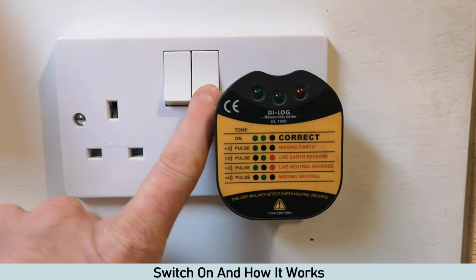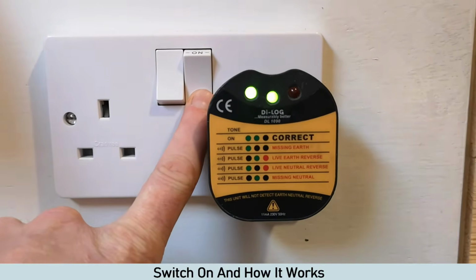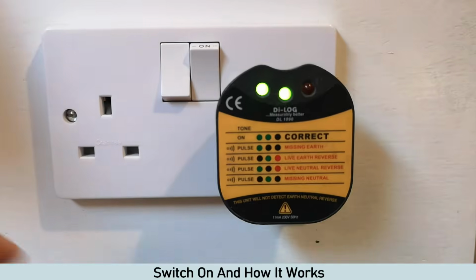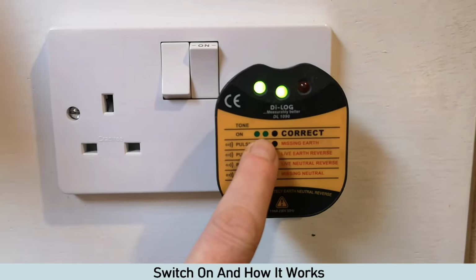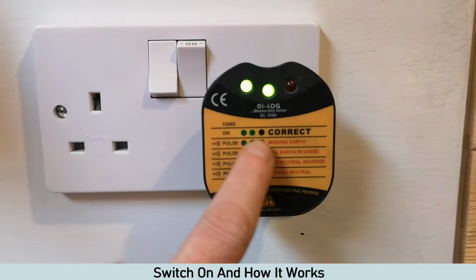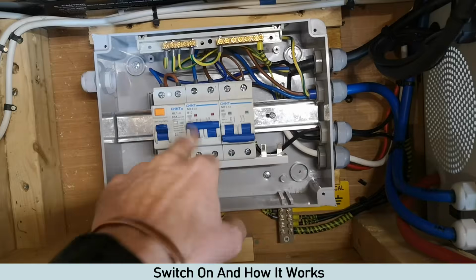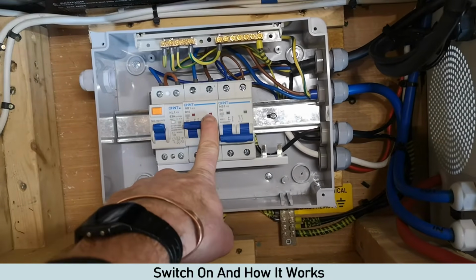If I switch that on, ta-da! So that means correct. So two green lights, as you can see there, is correct. So what I'll do now is isolate the hookup, just to recreate either an RCD that trips, or the hookup's unplugged, or the breaker's turned off.